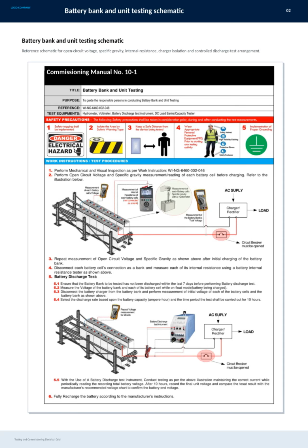Here we have the battery bank and unit testing schematic, which is essential for the testing and commissioning of the electrical grid. This schematic serves as a reference for several critical tests, including measuring the open circuit voltage, checking specific gravity, assessing internal resistance, ensuring charger isolation, and conducting controlled discharge tests. Each of these tests ensures the battery system operates reliably and efficiently before it is fully commissioned. This detailed approach helps us maintain system integrity and performance throughout its life cycle.